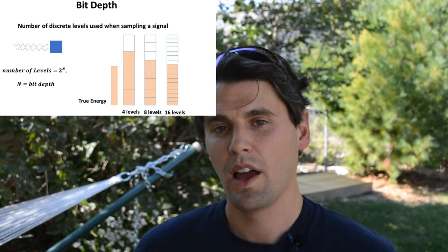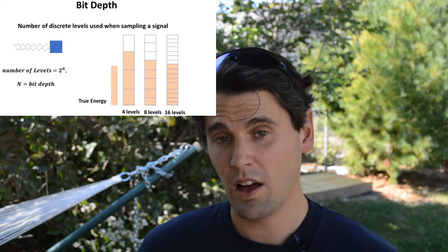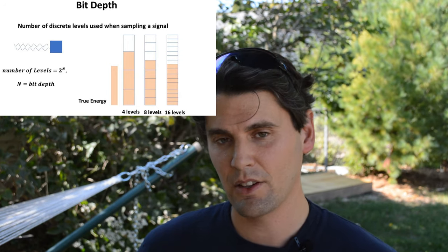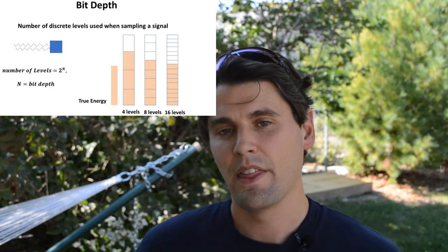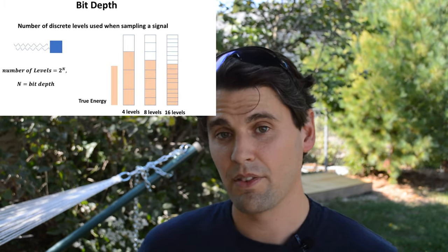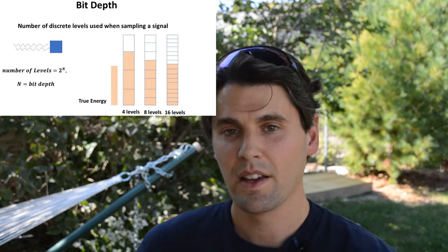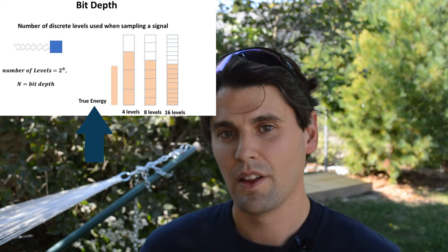That's the same thing that we can do if we increase what's called the bit depth, or the number of samples that we have. If we have a digital system, what's actually happening is we have an analog electric signal coming in and we need to convert that signal to a number. On an x-ray system, that signal on a digital x-ray system is going to be related to the energy that's deposited in the x-ray detector. So we have an analog electric signal and we need to convert it to a number by comparing our unit of measurement to the x-ray energy.